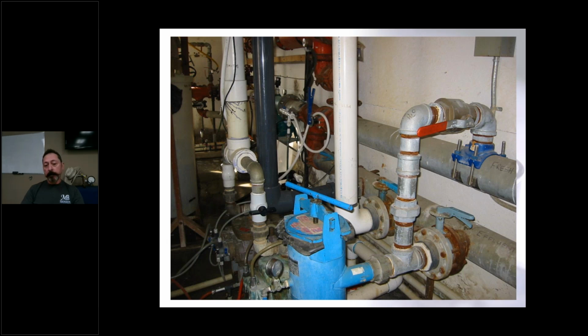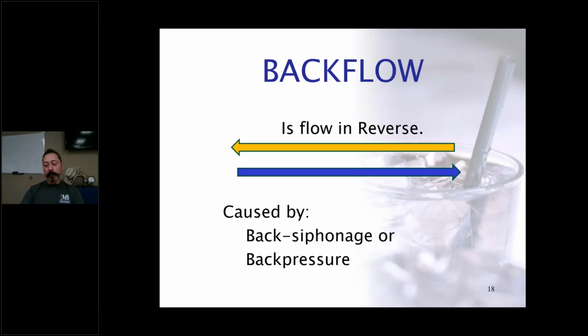And sometimes there are connections that are more complex than a garden hose. In this case, we've got a fresh water system here, which is our potable water system. And this is treated effluent from a sewer plant that is used for irrigation purposes. So it's treated effluent, but they're cross connected between the drinking water supply and the treated sewer effluent, including this blue item over here, which is a chemical injector. So it's a severe hazard cross connection that is a little bit more complicated, but that's something that could be in an industrial application, even though you're in a small utility. So those are examples of cross connections.